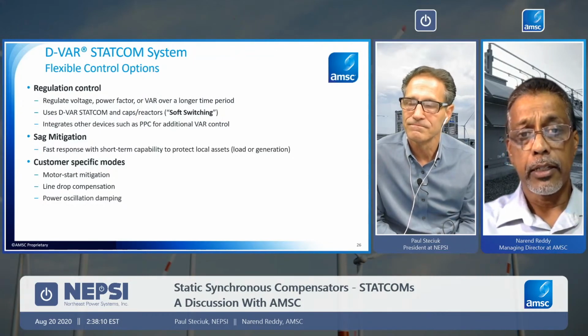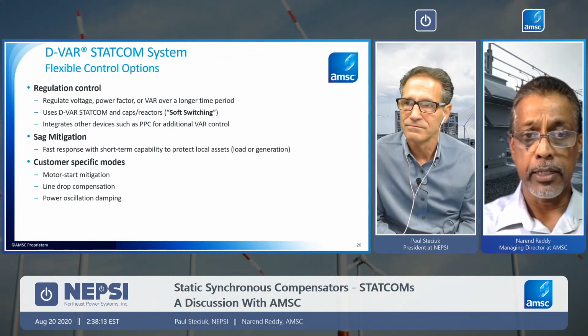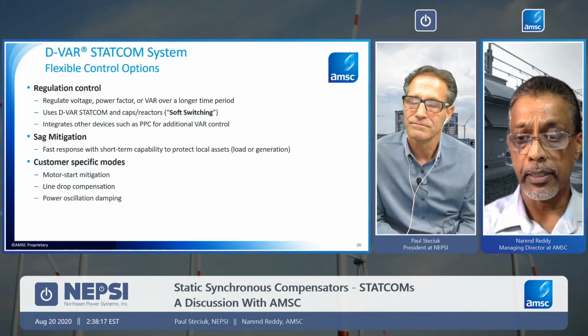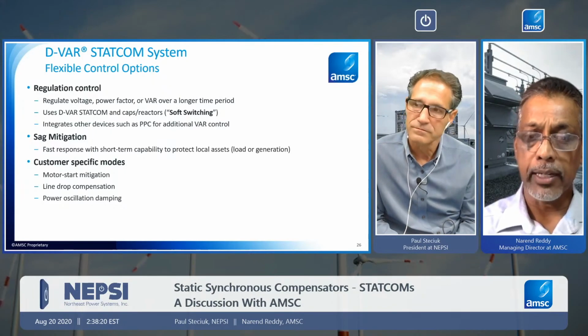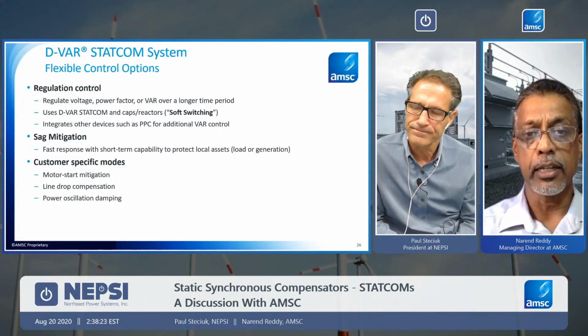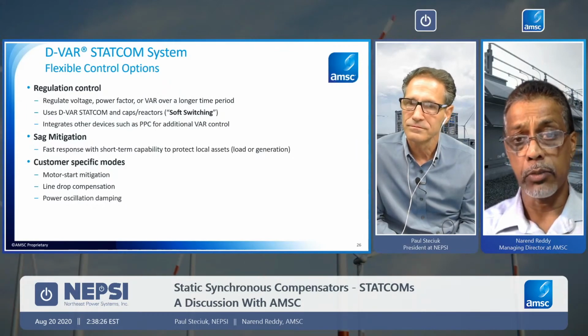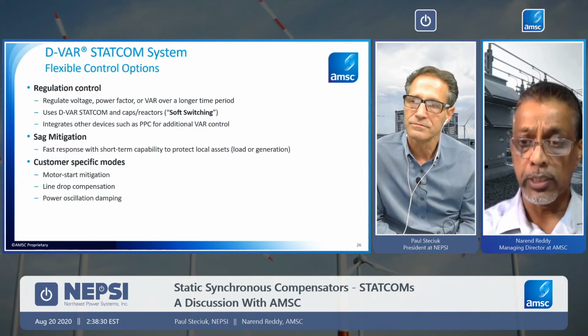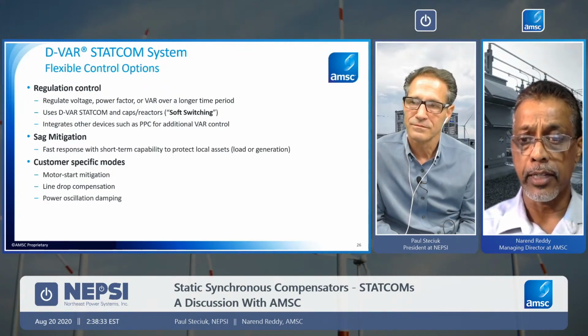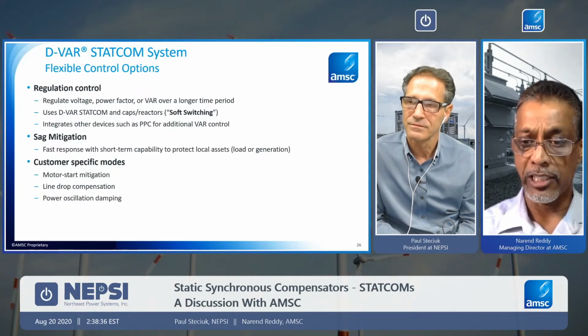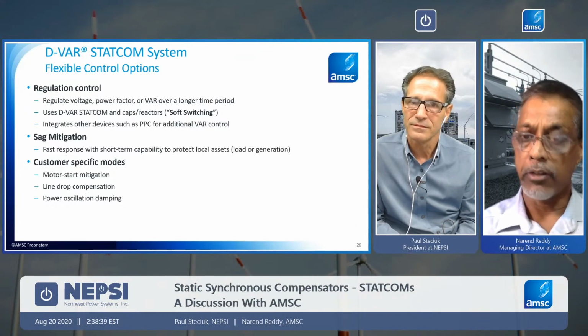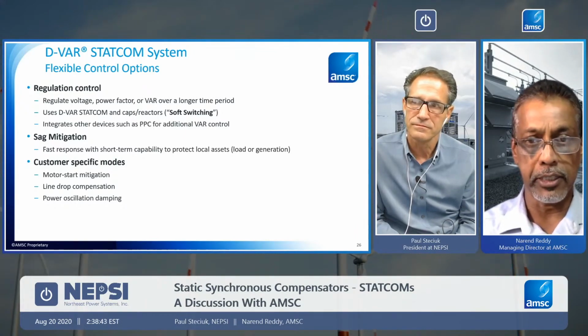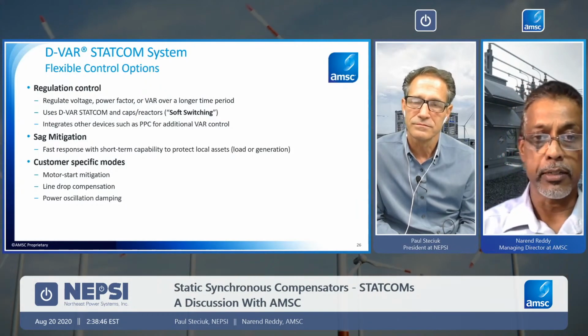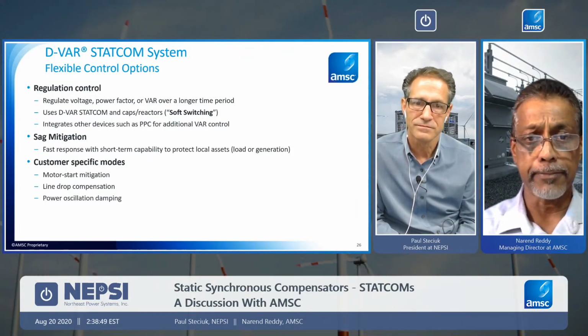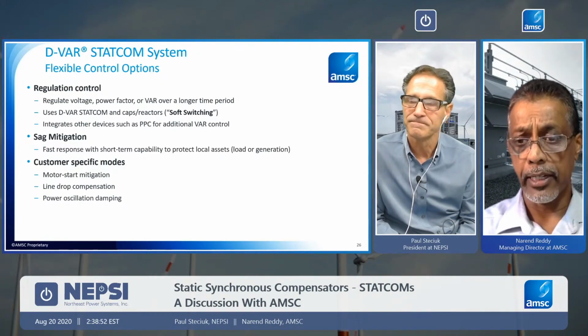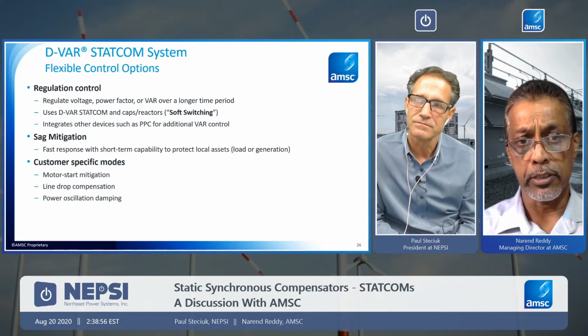Now, the dvar STATCOM, as I mentioned, is a hybrid system, and we can expand the capability if there is more of a steady state requirement along with some dynamic requirement initially. We can use cap banks and reactor banks, and we use the concept of soft switching these, so that when these capacitors or reactors, which are switched on a chunky basis, are brought in or taken out of the system, there is no voltage change on the grid, which I'm sure you appreciate would happen otherwise, depending on the short circuit capacity. So the dvar dynamic capability is able to absorb a lot of that shock to the system.